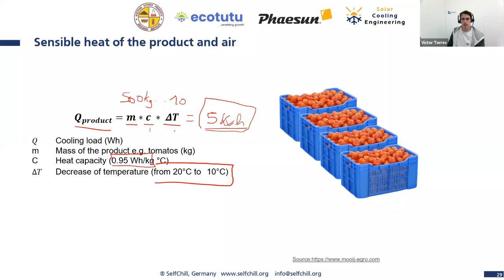But what is the limitation of this equation? If we cool the air down to lower temperatures, which is the case in our cold room, as soon as we reach saturation—this point here—following this line, at 26 degrees it is saturated. From now on, you're not only cooling the air, you're also condensing water, and condensing water requires a lot of energy. That's why we need to use the psychrometric chart to assess the energy required when hot air enters our cold room.